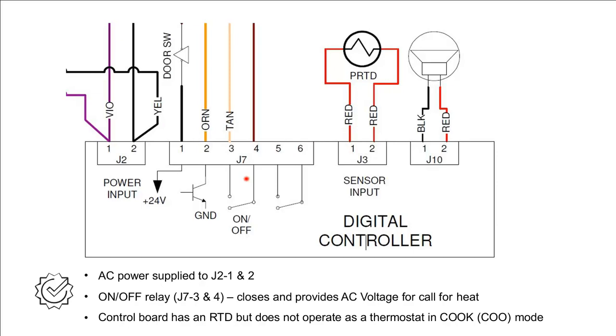When you push the on-off button on the front of the unit, this contact closes. We have voltage from our AC relay here. It will then flow through the relay and out of the brown. This signal is continuous. As soon as the unit is powered on, that is there. There is no break to it. The control board does not control that signal based on the temperature of the unit. It is a continuous output.